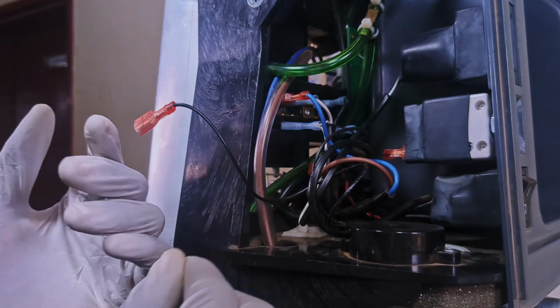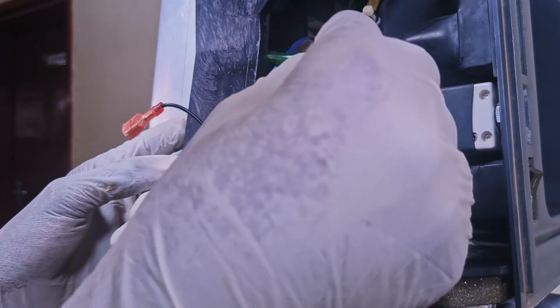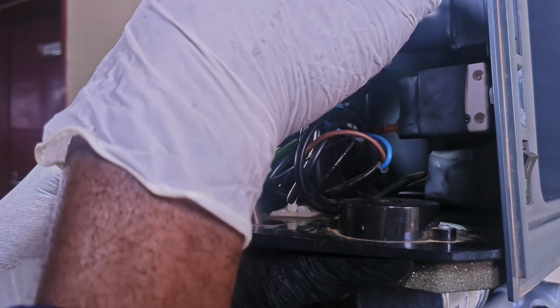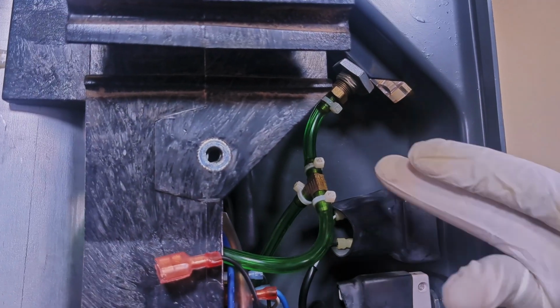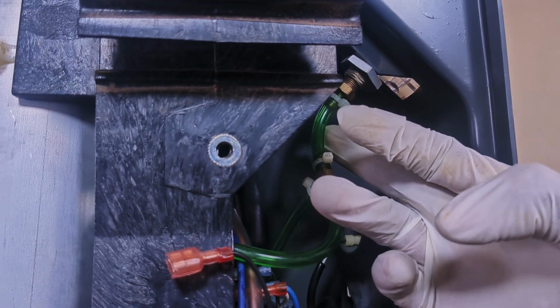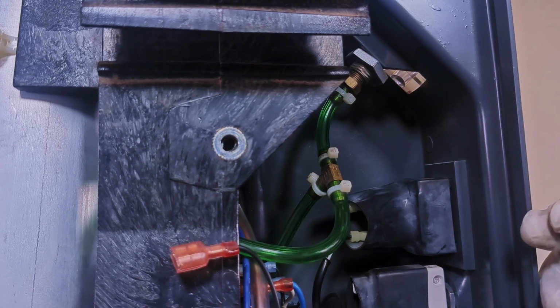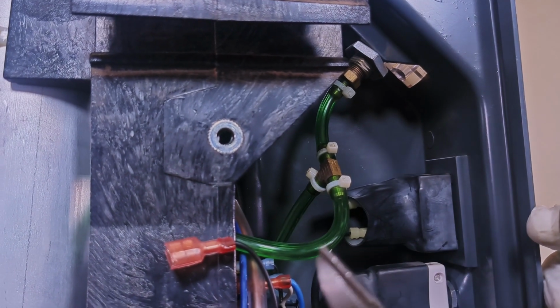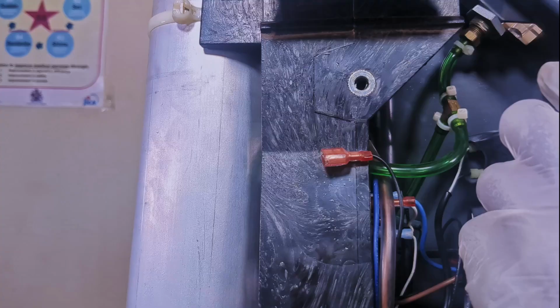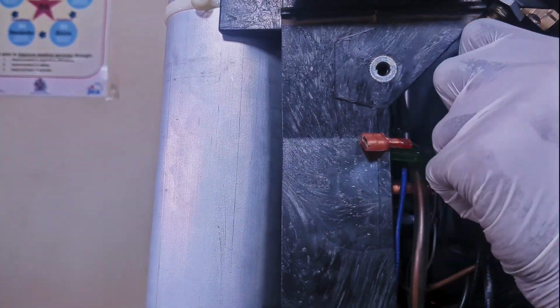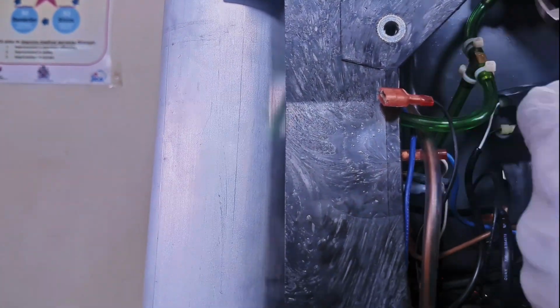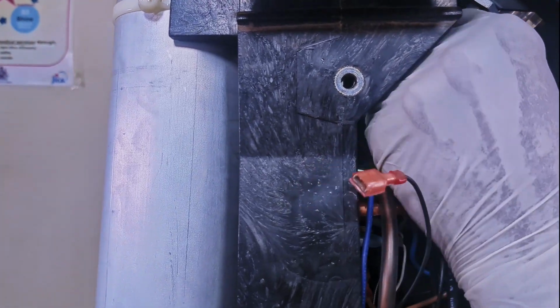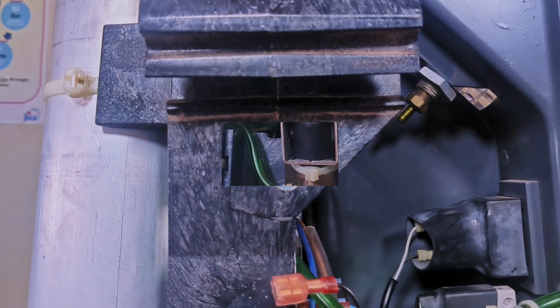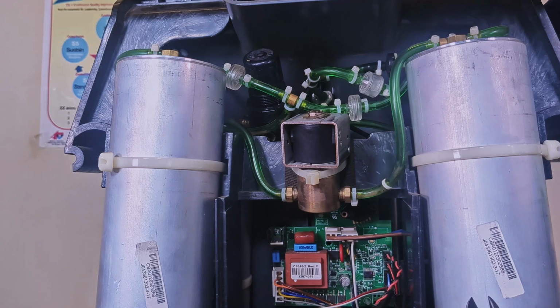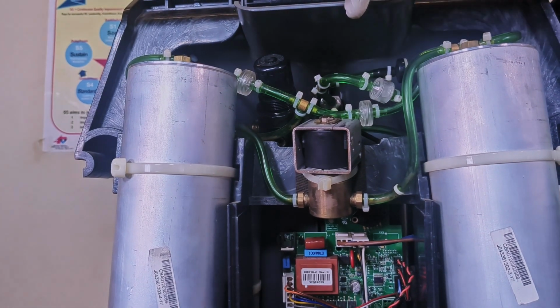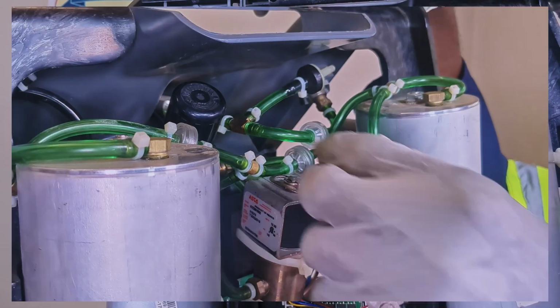So after disconnecting the power cables, I can now go ahead and disconnect the tubings. To disconnect this tubing, which goes to the flow meter inlet, I will use a cutter to cut the cable tie. Then next, I will disconnect the tubing that goes to the oxygen outlet port.